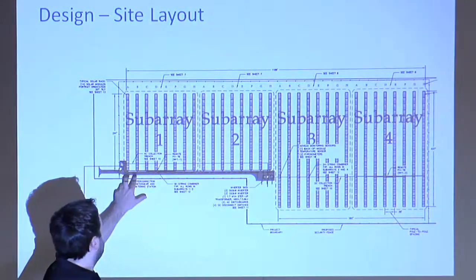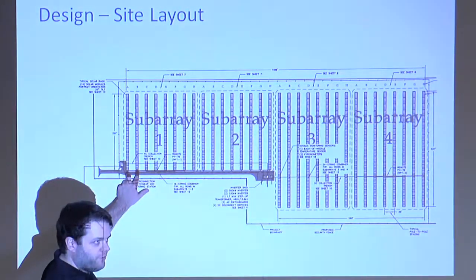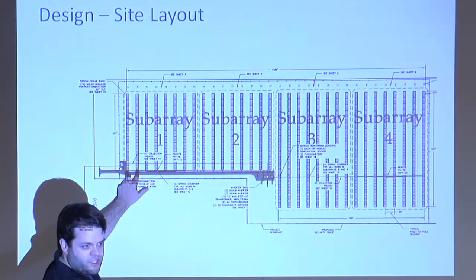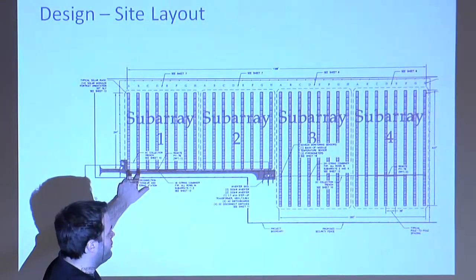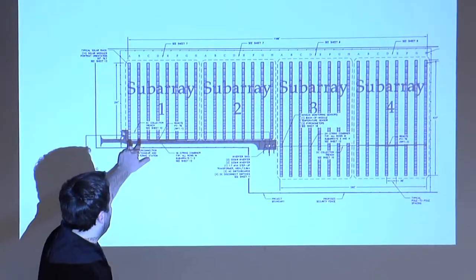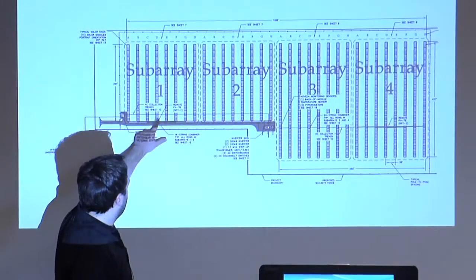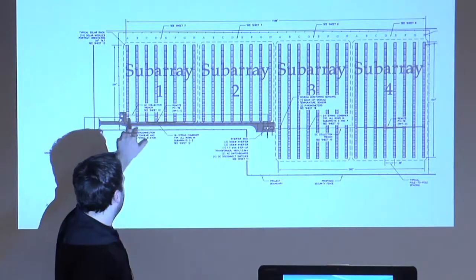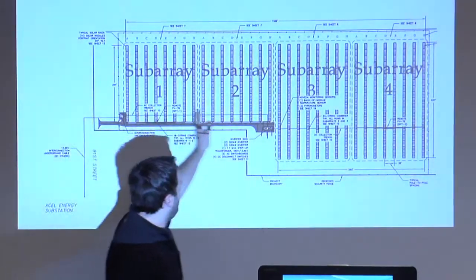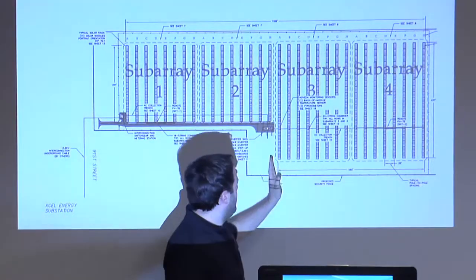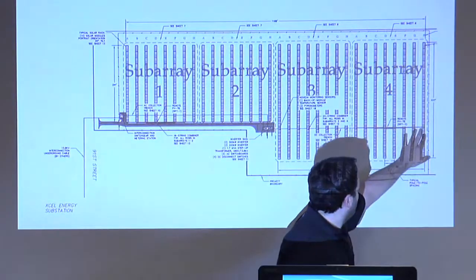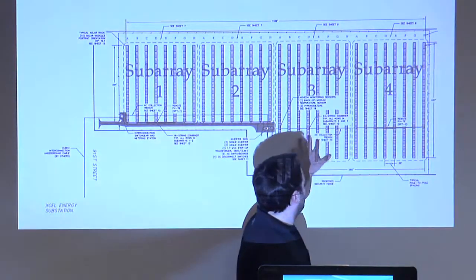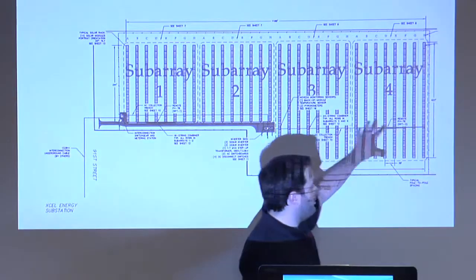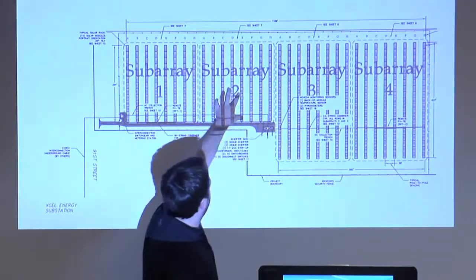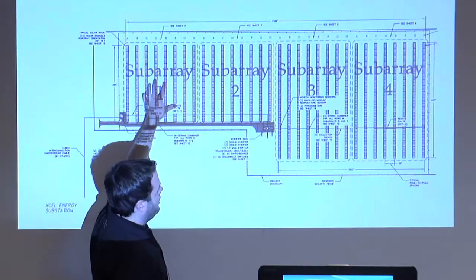So we spaced these rows for standard morning shading, so 9 to 3 winter solstice. Each one of these rows has a combiner box on the end of it, so we have 16, 16, 16, all the way down for the first 2 subarrays, and then 24 around these second 2 subarrays. So this is 500 kilowatts, 500, 333, and 333.